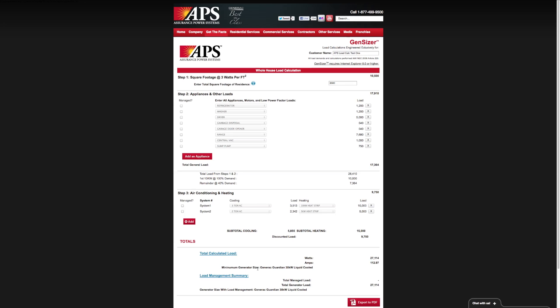Based on that, it's telling us for the whole home, the minimum generator size needed would be a 30 kW generator system. Now right under that, you can see a load management summary. Under total managed load, you can see that we don't have anything selected here, so it's giving us the same size generator under this scenario.